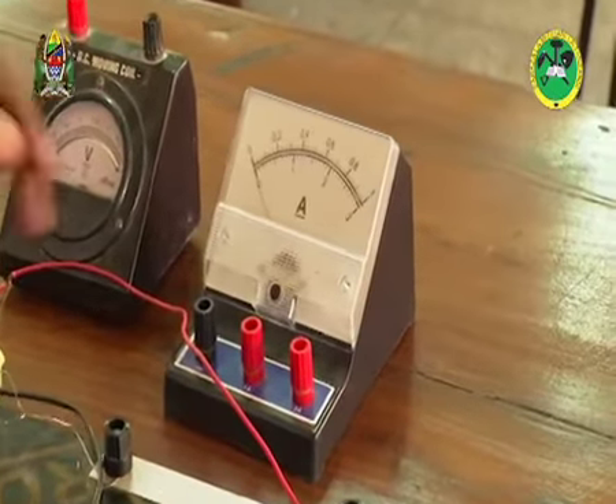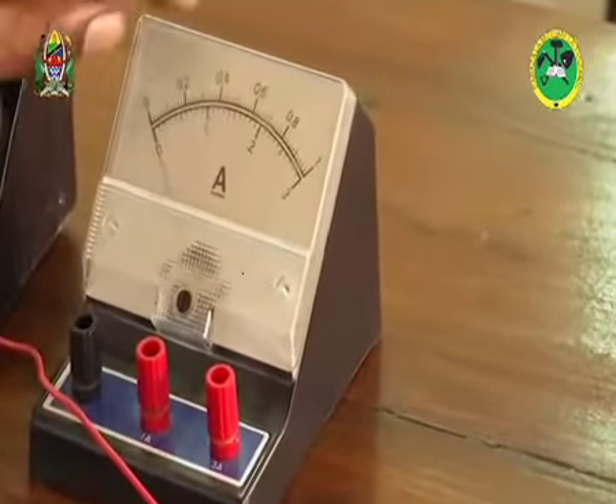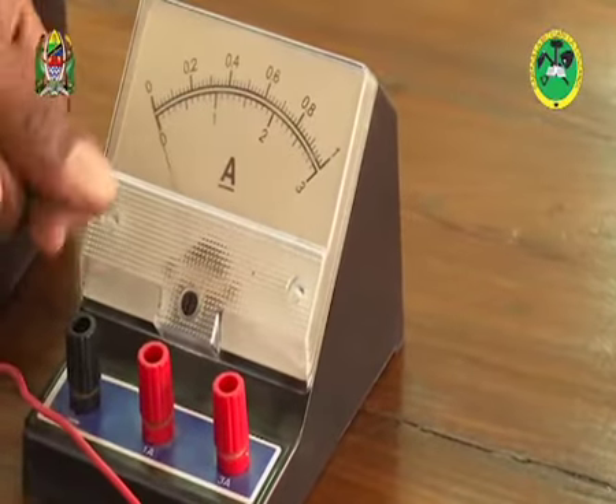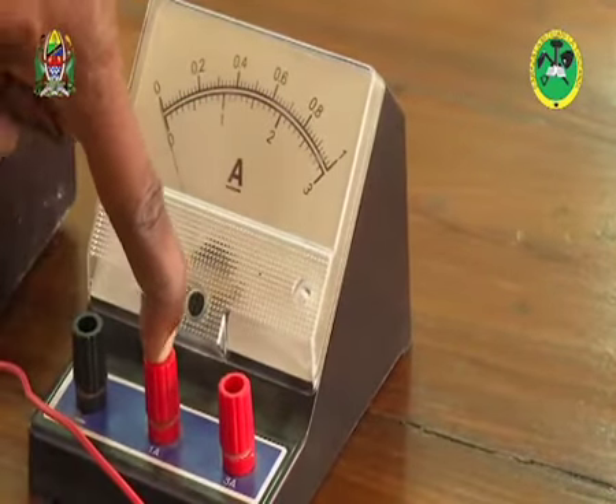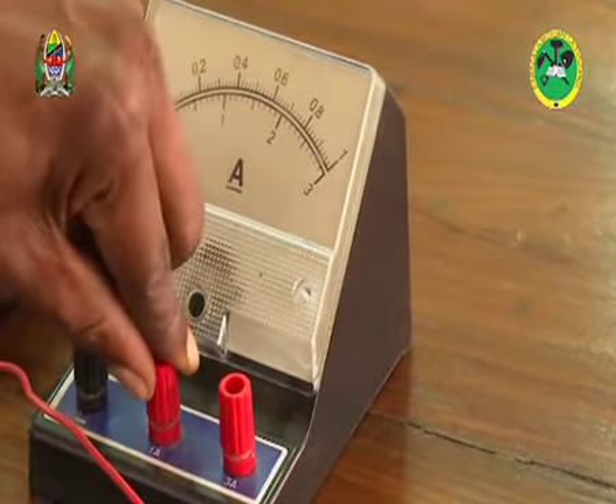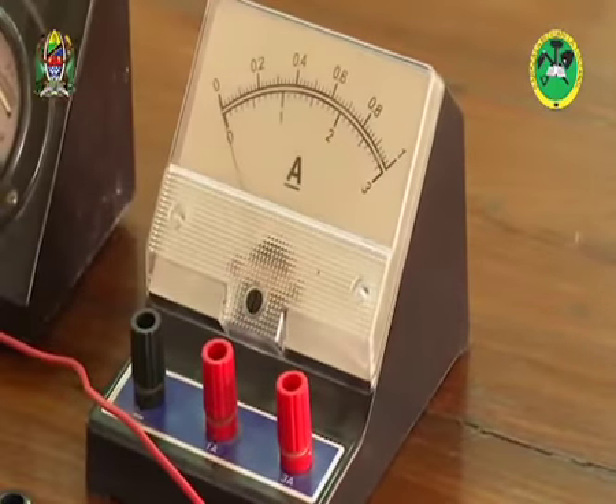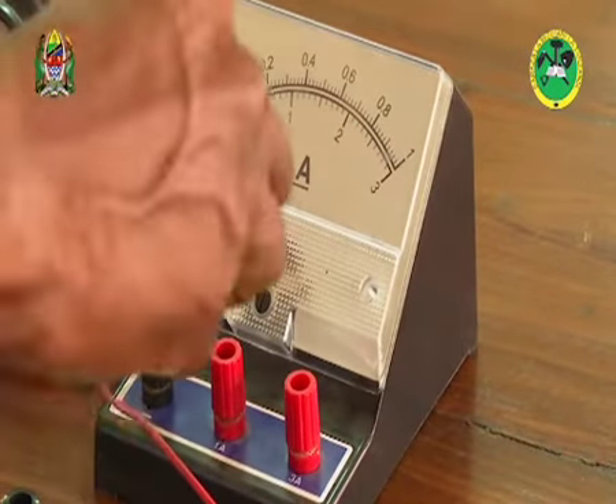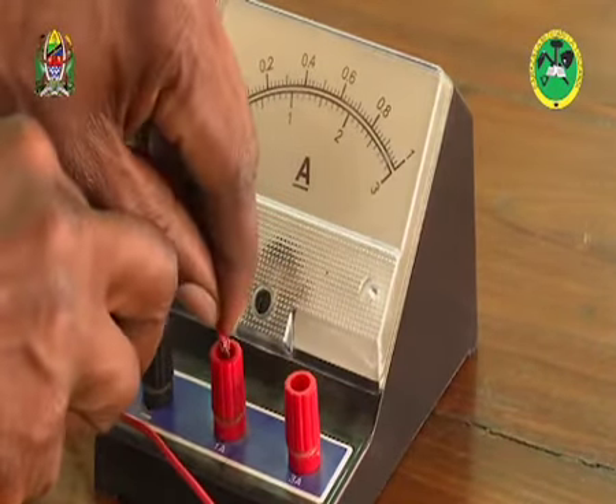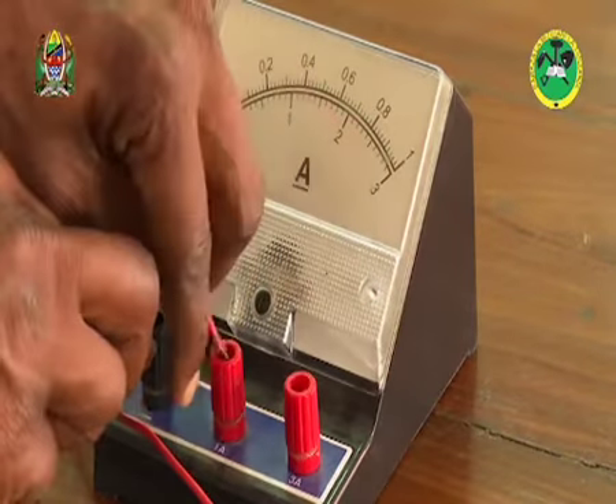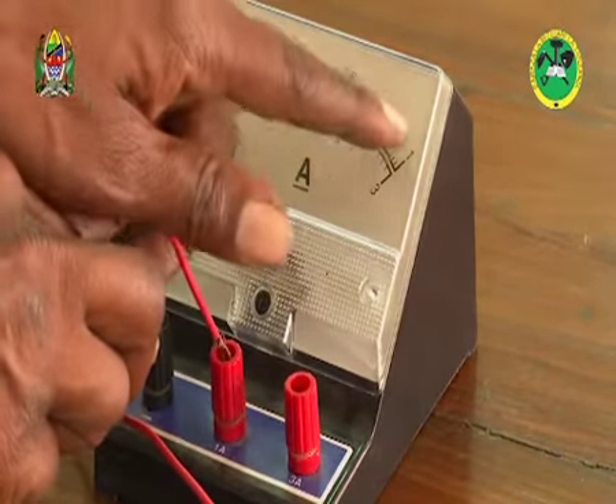So have a look here. If you are using the top one, then you need to connect between this, which is the common one, and this knob which is showing the highest possible range, 1 here. So if I connect this terminal and that terminal, then I use the top one because this is the 1 range. I keep reading up here.